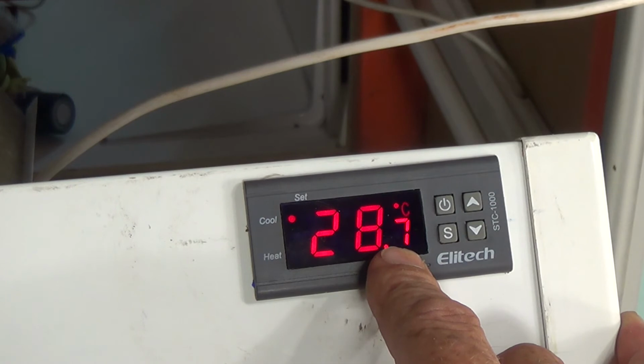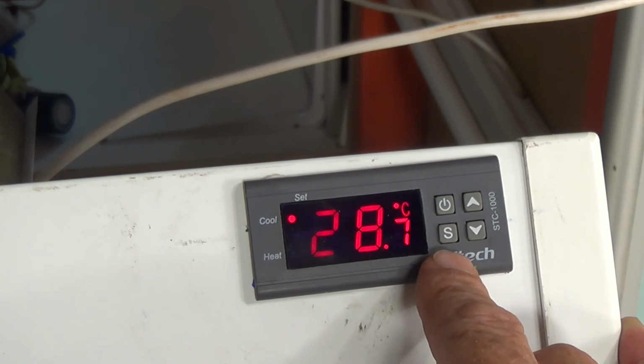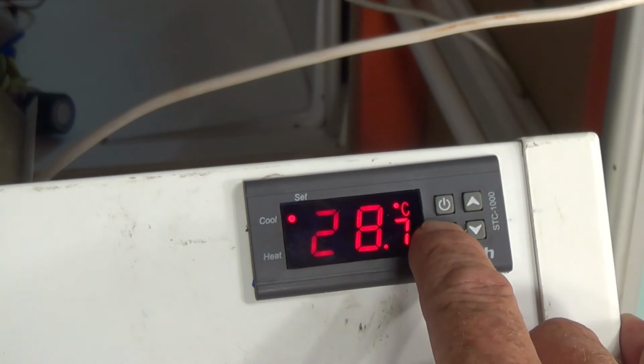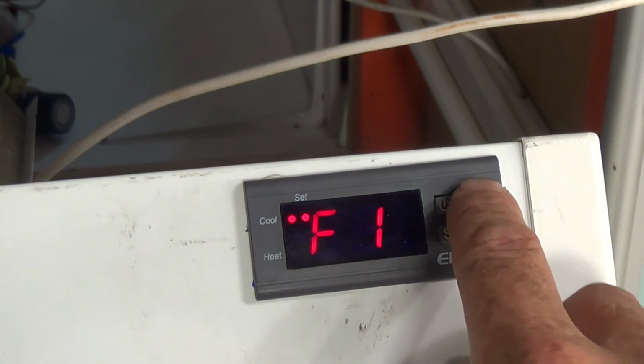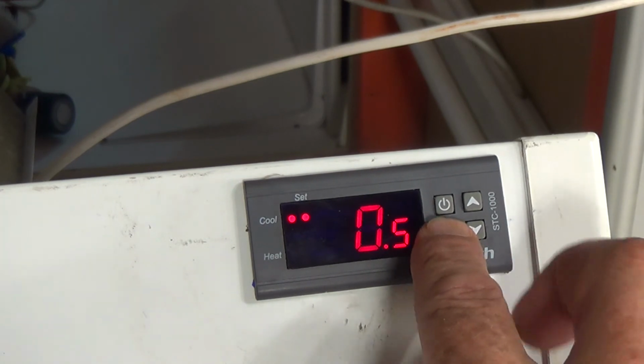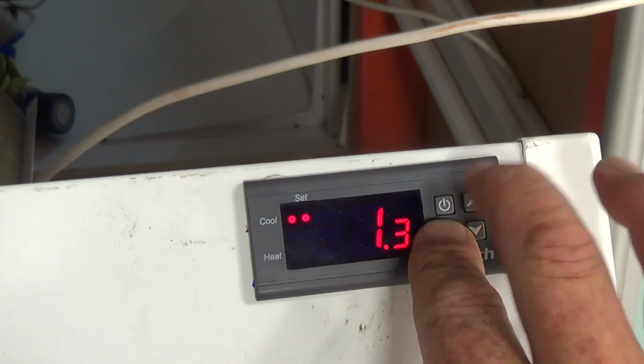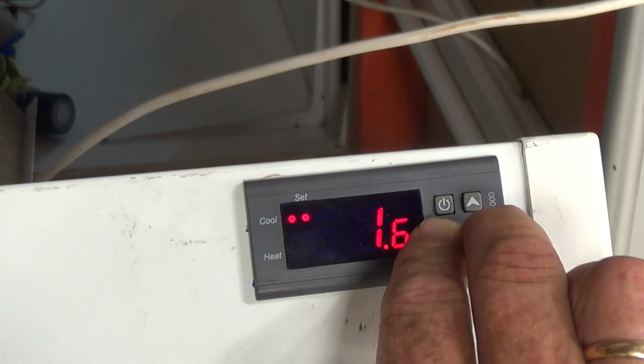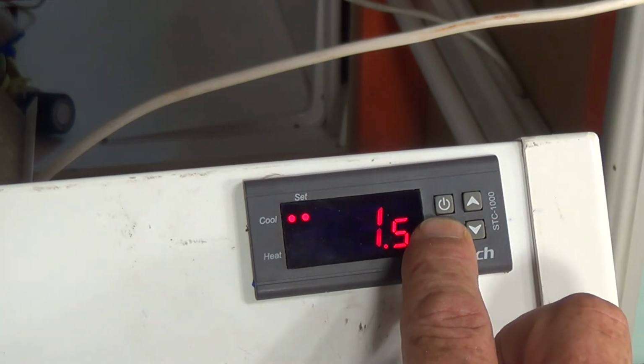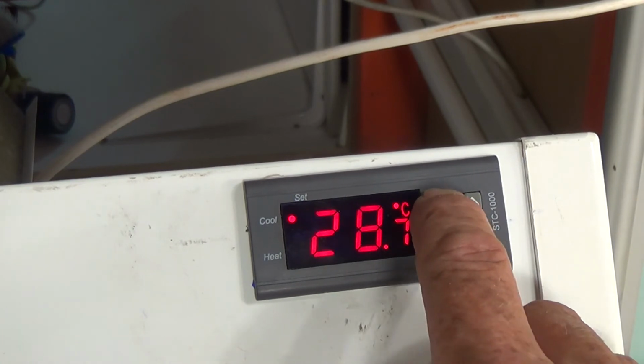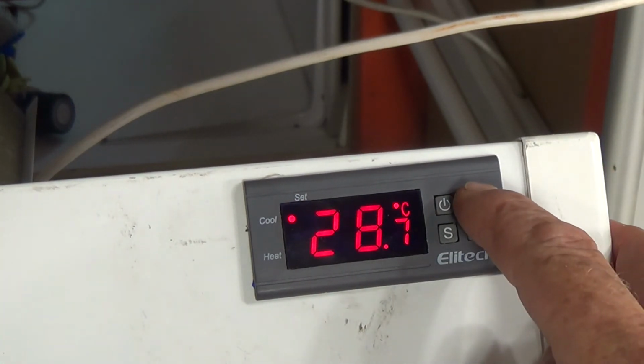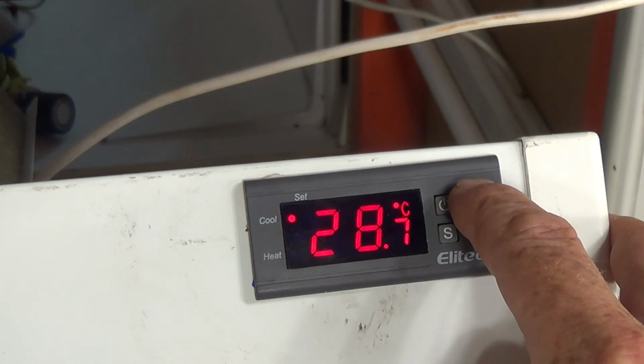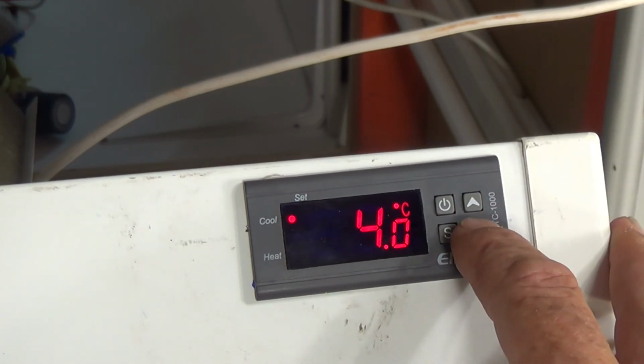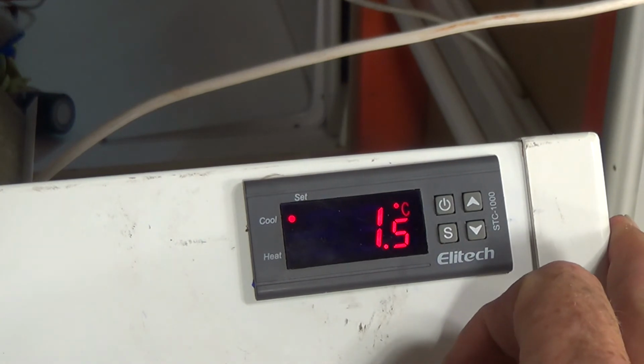This means that the compressor will turn off at 4 degrees but will come back on at 5.5 degrees. So to do this, you need to go back into setup mode, hold the set button for 3 seconds, change this to F2, hold down the set, and we'll try it at 1.5 to start with. Remember the setting, press the on-off button. So now we have a temperature set at 4 degrees and a variation or differential of 1.5.